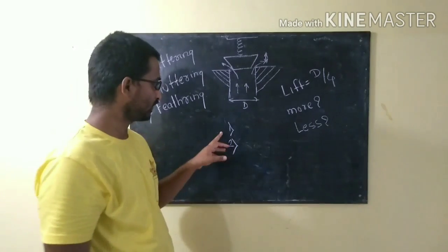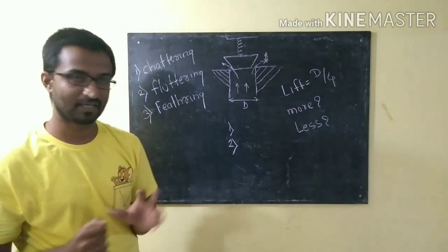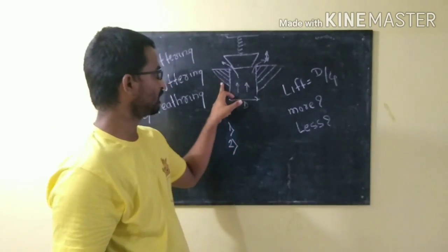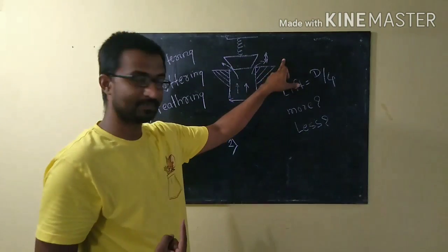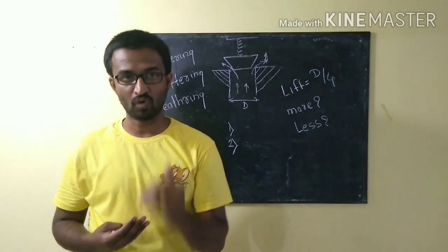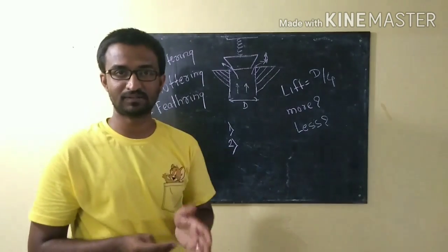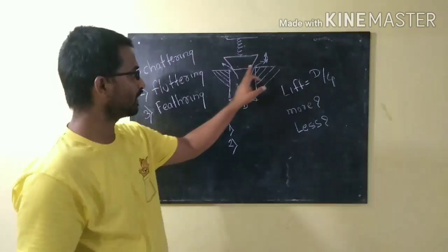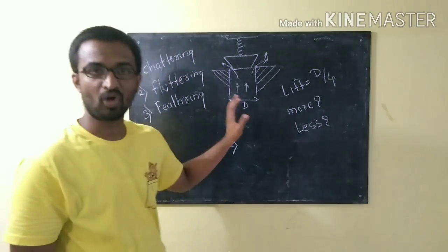I told you two reasons. If the safety valve diameter is not proper and is more, the thickness will be more and the clamping force reduces, because of which steam can leak. And second, if you are not using proper water, or the water has sediments or other impurities, they get accumulated over here and a thin film starts leaking. That we call feathering.